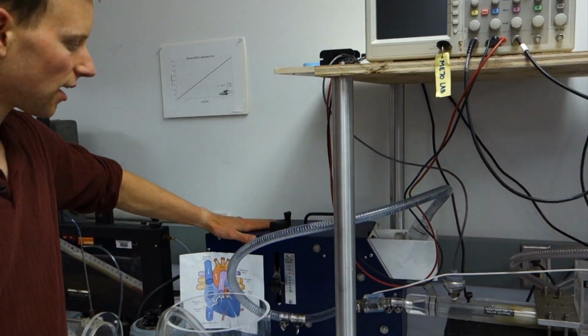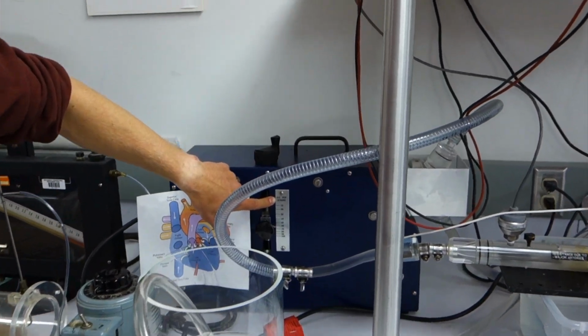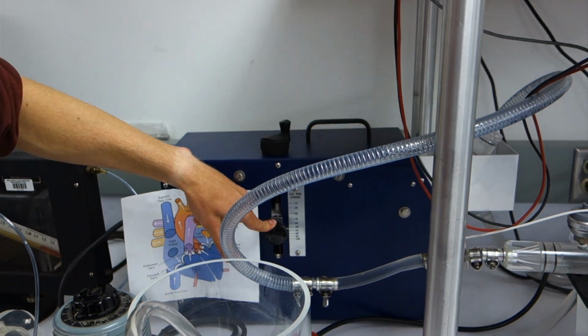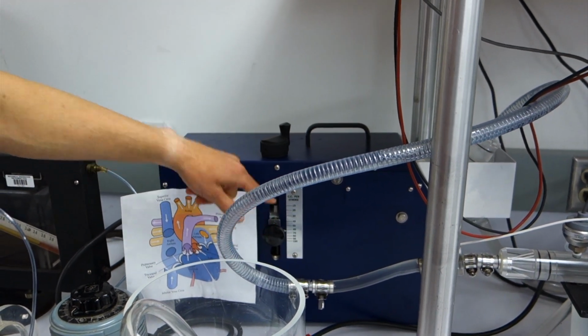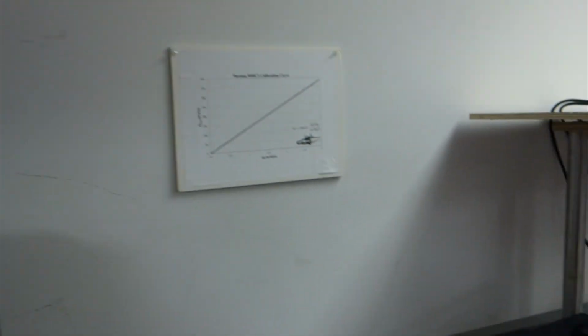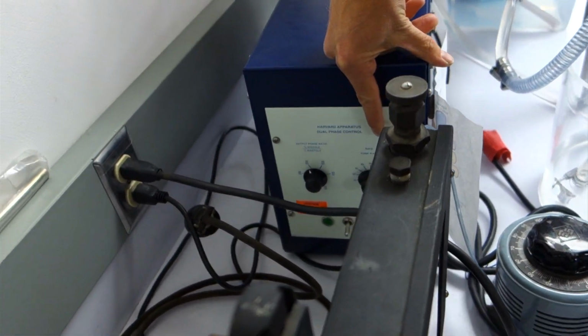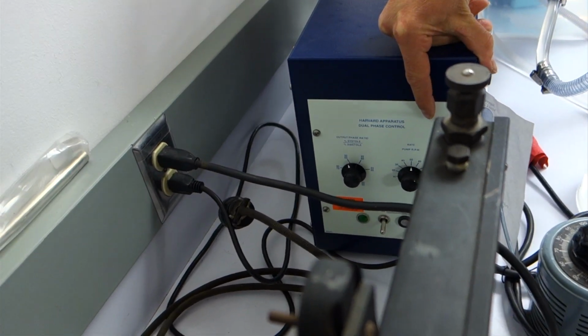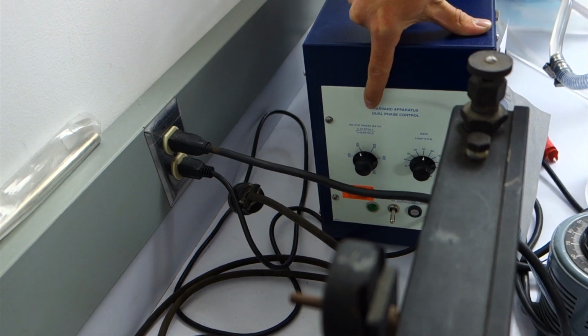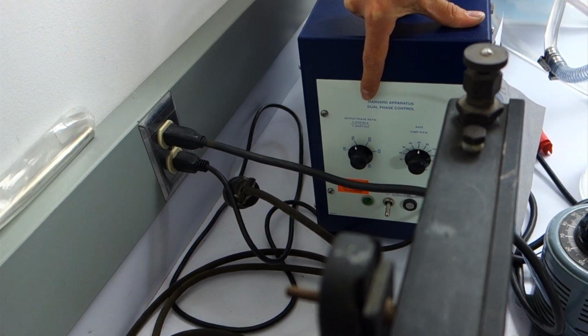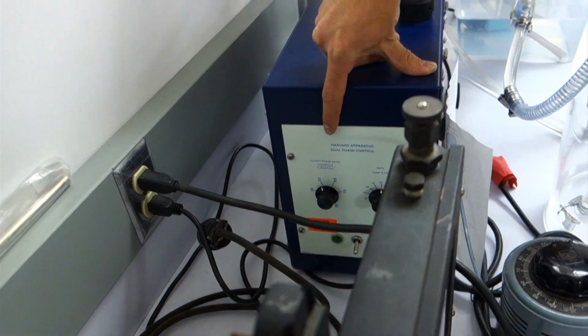There are a few knobs on the heart. We have a cubic centimeters per stroke knob. This represents the volume of the heart, so how big an animal we're going to be simulating. We have the pump rate. It's not worth looking at too much depth. Maybe it is. The pump rate is given in BPM, so we're looking at 60 or 50 BPM right now, so a little less than 1 hertz. And then the output phase ratio, percent systole over percent diastole. This is the amount of time spent during the systolic part and diastolic part respectively.